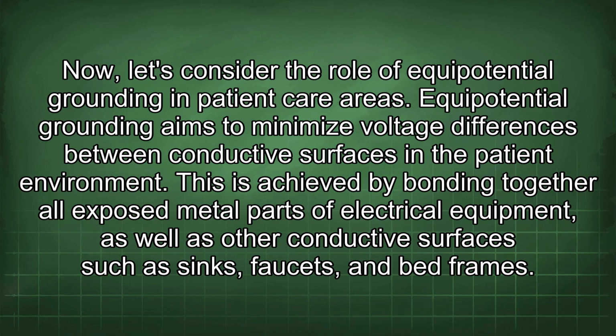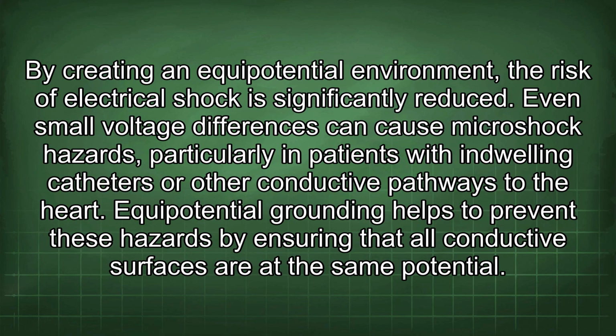Equipotential grounding aims to minimize voltage differences between conductive surfaces in the patient environment. This is achieved by bonding together all exposed metal parts of electrical equipment, as well as other conductive surfaces such as sinks, faucets, and bed frames. By creating an equipotential environment, the risk of electrical shock is significantly reduced. Even small voltage differences can cause microshock hazards, particularly in patients with indwelling catheters or other conductive pathways to the heart. Equipotential grounding helps to prevent these hazards by ensuring that all conductive surfaces are at the same potential.